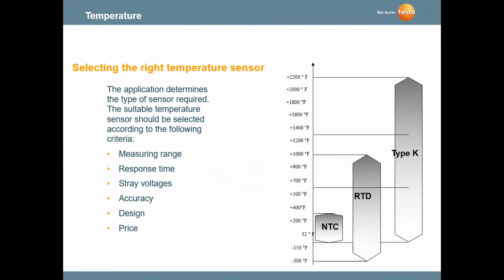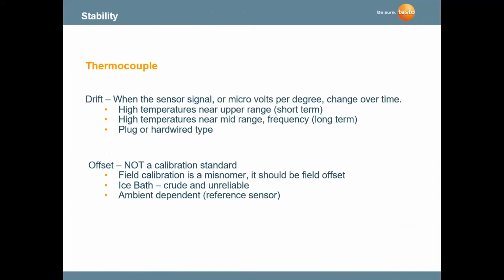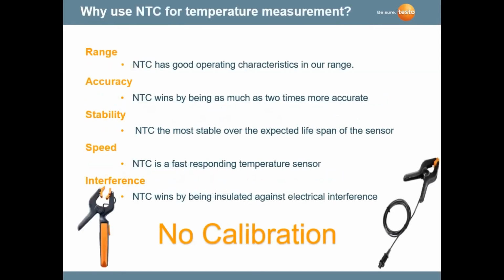So the NTC sensor is used a lot in low temperature applications, whereas the type K probe is used a lot in heating applications or just general temperature measurement. But the real accuracy is at the lower range where the NTC probe is. So the thing about thermocouples is thermocouples do drift over time. They do need to be calibrated. And I'm not so sure a lot of us are calibrating our thermocouples in the field. They typically need to be calibrated once a year. That's a tough thing to do when you're in the field.